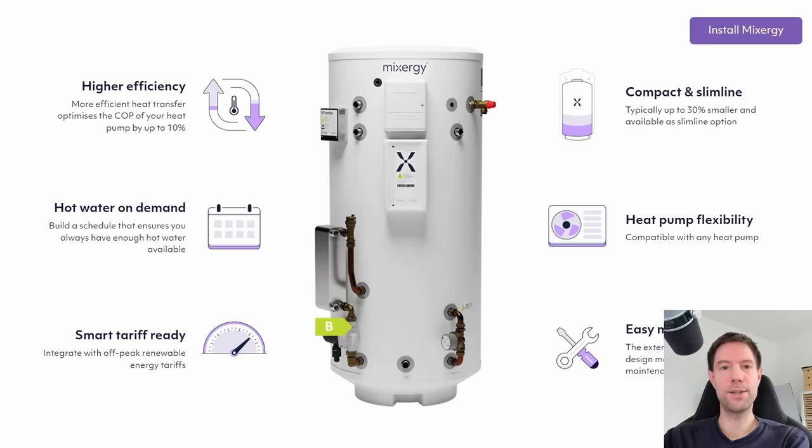If you already use an unvented cylinder, replacing it with a Mixergy cylinder could give you a small efficiency gain. Mixergy cylinders work in a slightly different way to a standard unvented cylinder. Normally an unvented cylinder heats the water from the bottom and fills the entire cylinder. Whereas a Mixergy tank heats from the top and pushes the hot water down as it fills up, which means if you only use, say, half a cylinder each day, the Mixergy tank will only fill up to halfway. That means there's less hot water to lose heat, so you lose less energy during the day — and therefore you need less energy to heat it back up again the following day, leading to lower bills and lower energy usage.